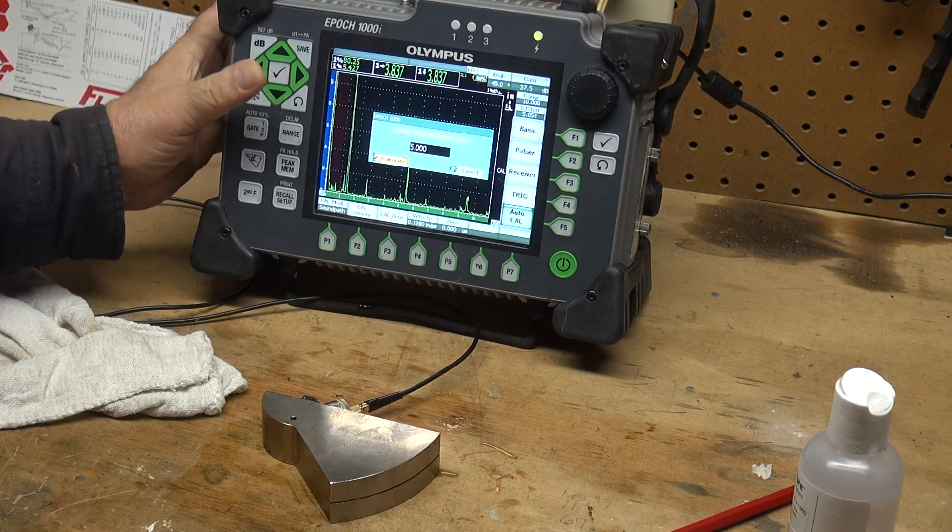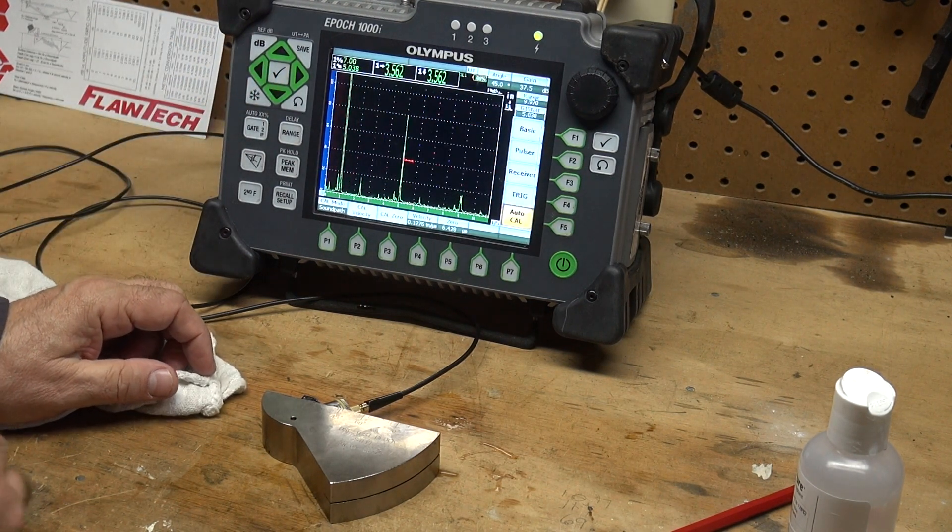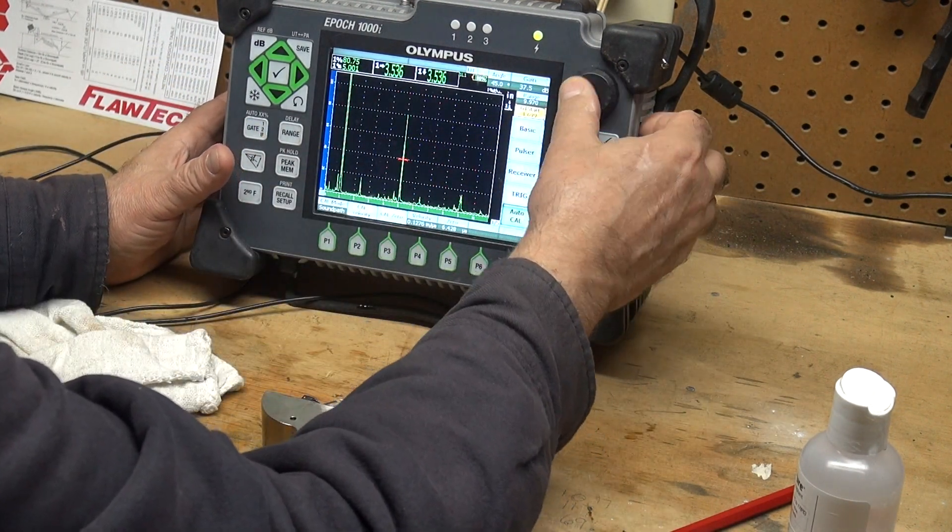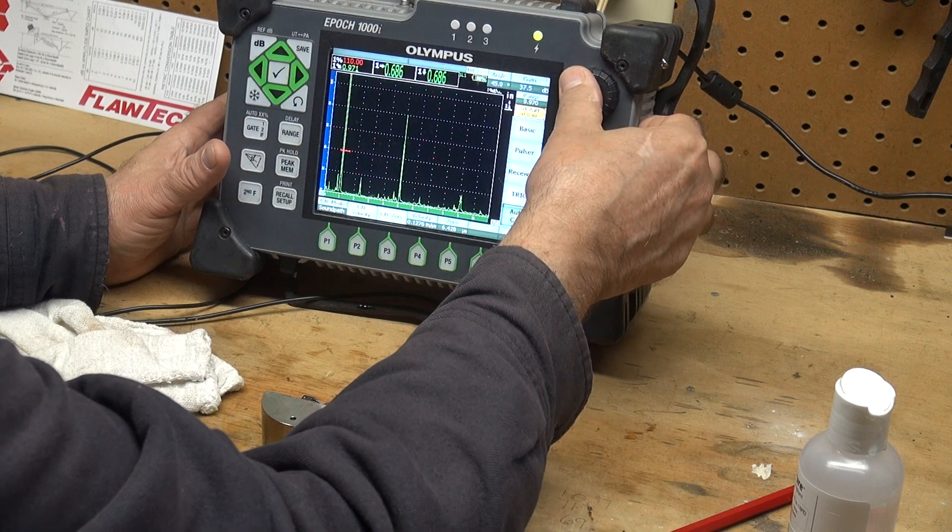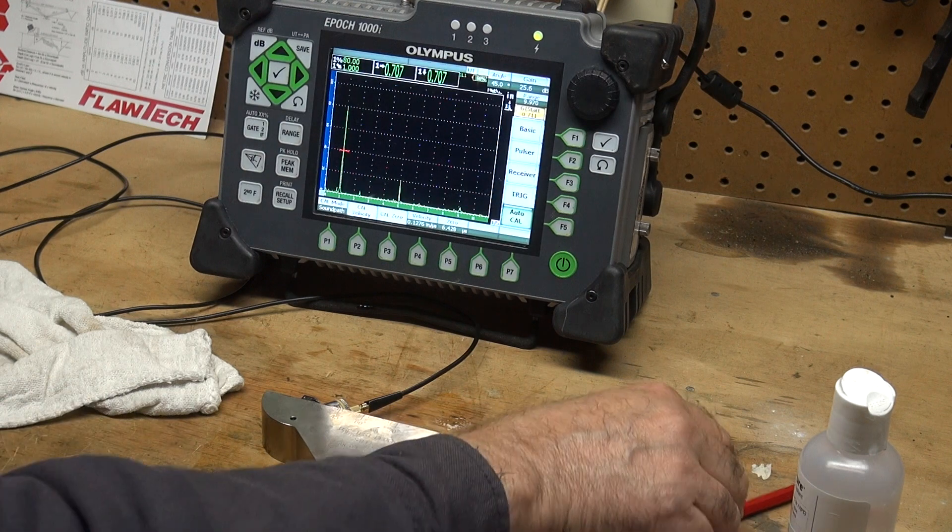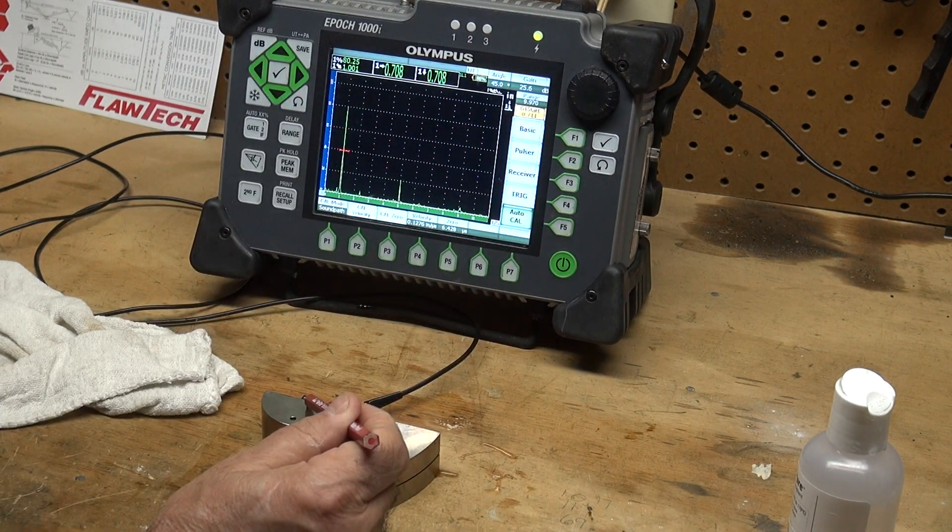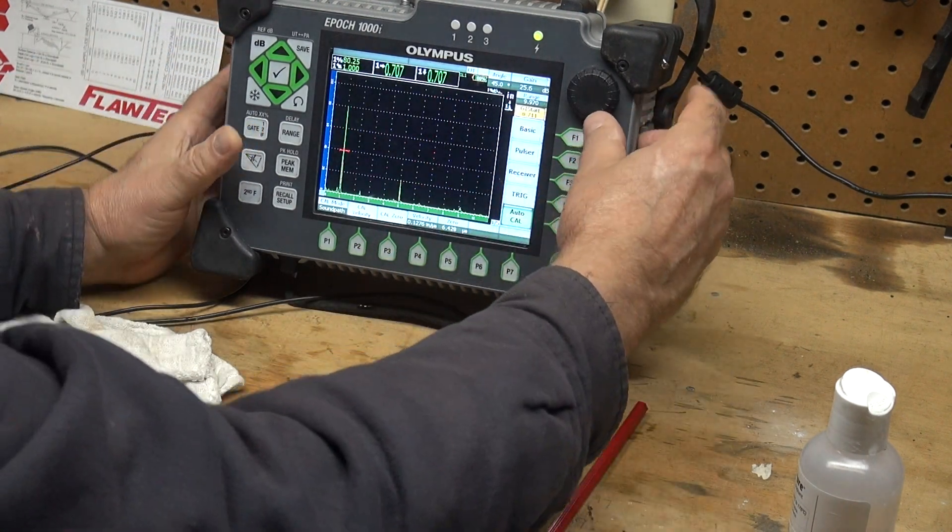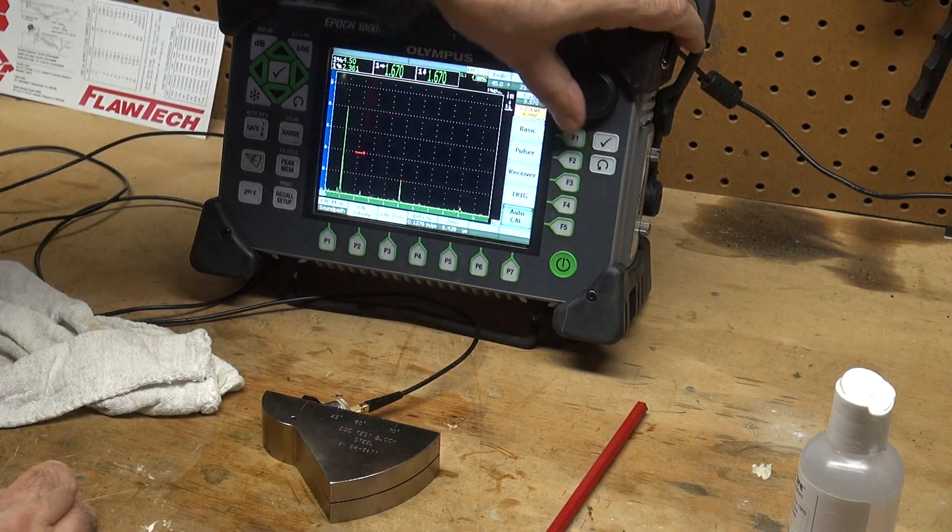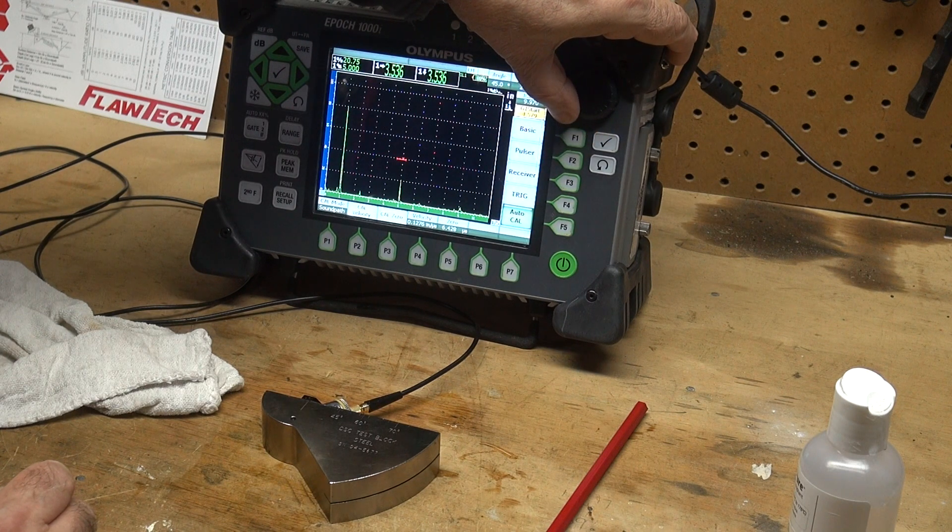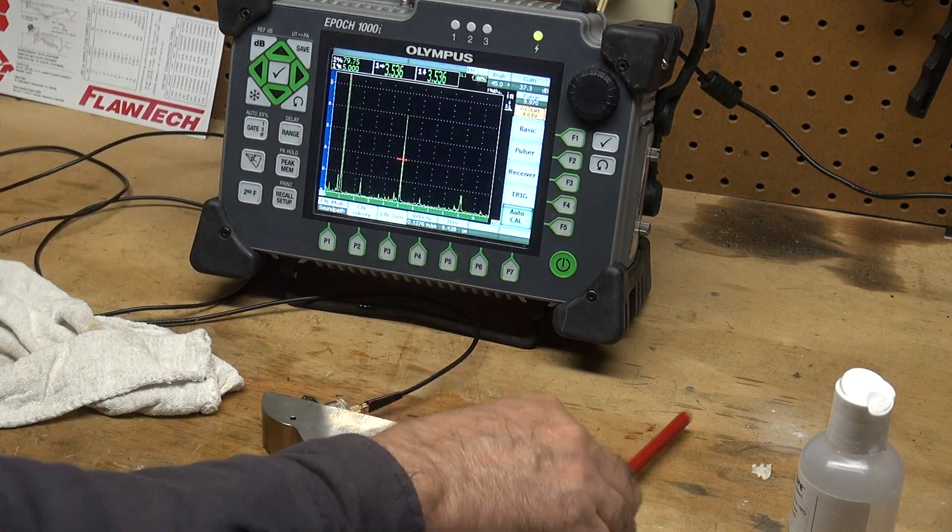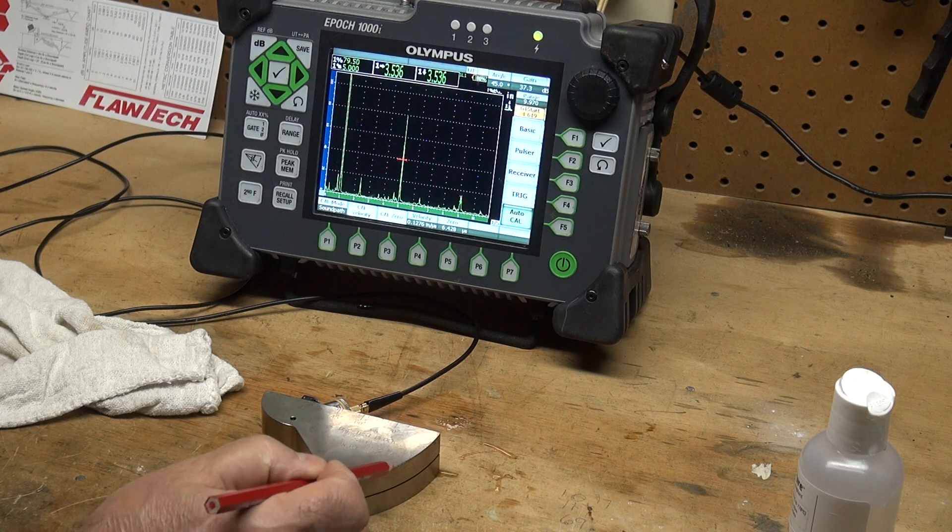And there we go, calibrated. So now I'm calibrated. Let's take the gate and run it over here, my first reflector, my first radius. We will see, take it to 80 percent full screen height, that's a one-inch sound path. Move that gate over to capture this, take it to 80 percent full screen height, and what we see is five-inch sound path, one inch plus three inches is four, plus one more, five inches.